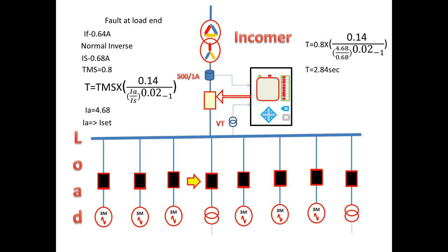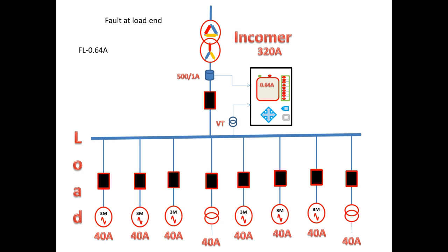The relay will give a trip command to the breaker. This is a heavy fault for the outgoing feeder, and waiting approximately 3 seconds is very dangerous for the outgoing feeder as well as the incoming transformer. So using IDMT for this fault at load end is not preferable.